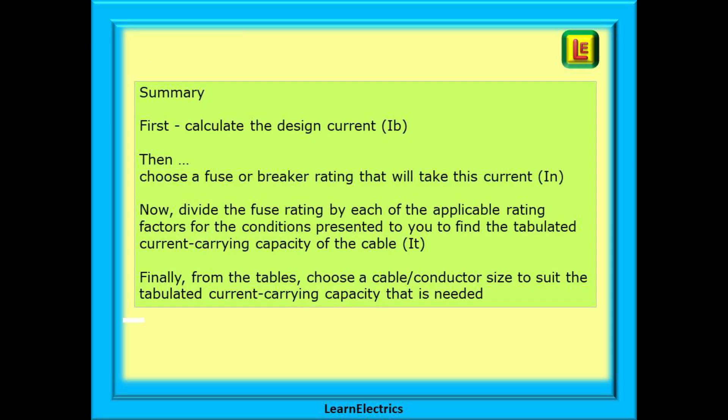In summary then, first calculate the design current, IB. Then choose a fuse or breaker rating that will take this value of current, IN. Now, divide the fuse rating by each of the applicable rating factors for the conditions presented to you and you will find the tabulated current carrying capacity, IT. Finally, from the tables, choose a cable or conductor size to suit the tabulated current carrying capacity that is needed. And that is it.